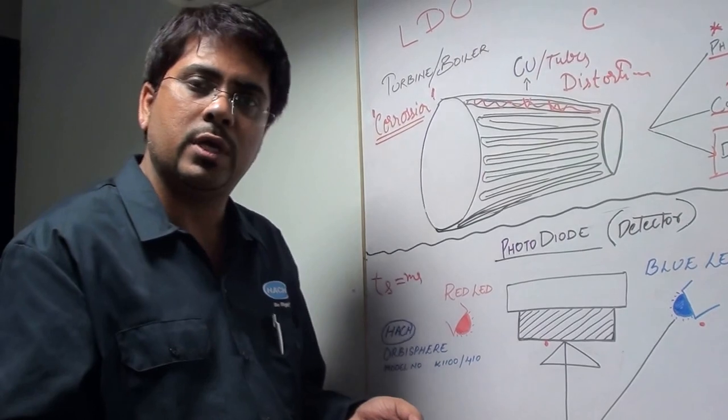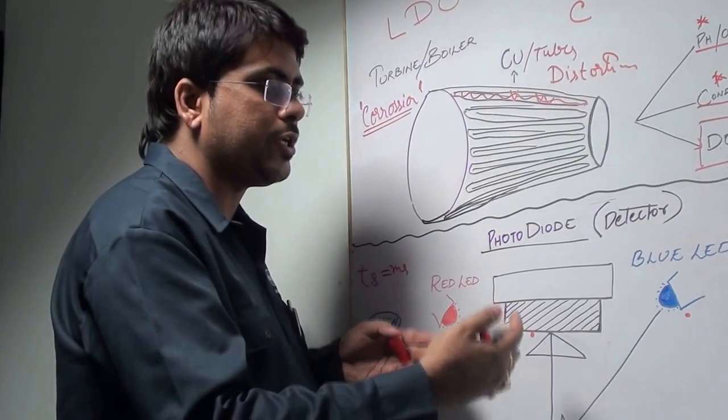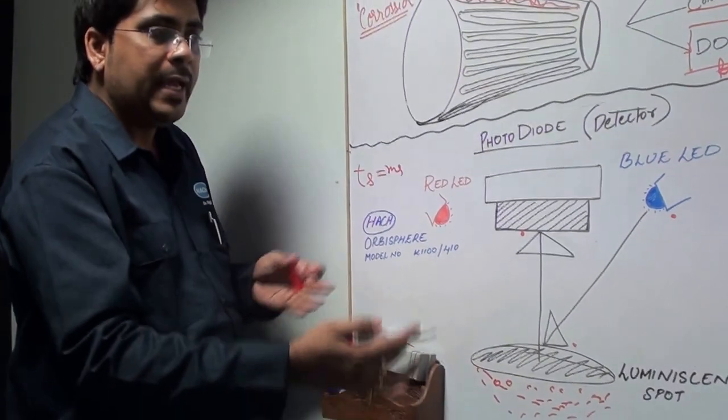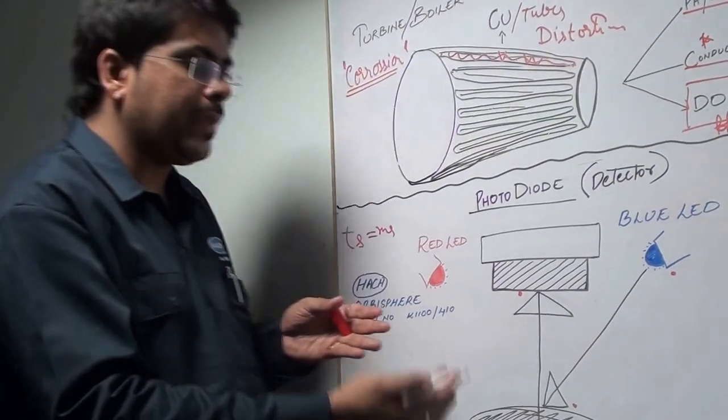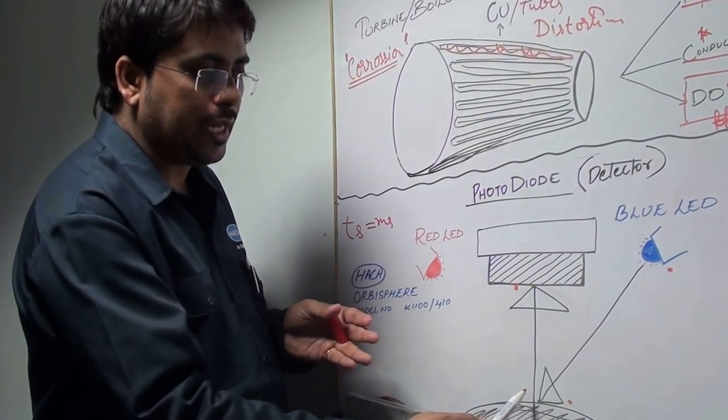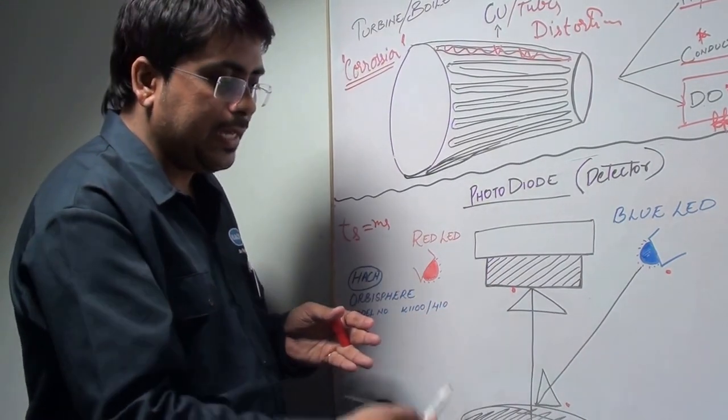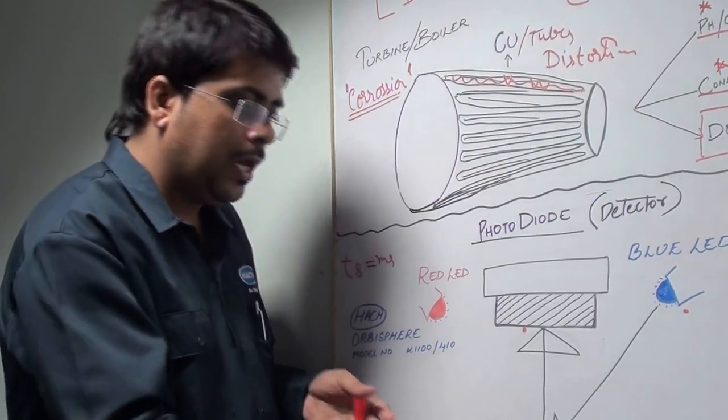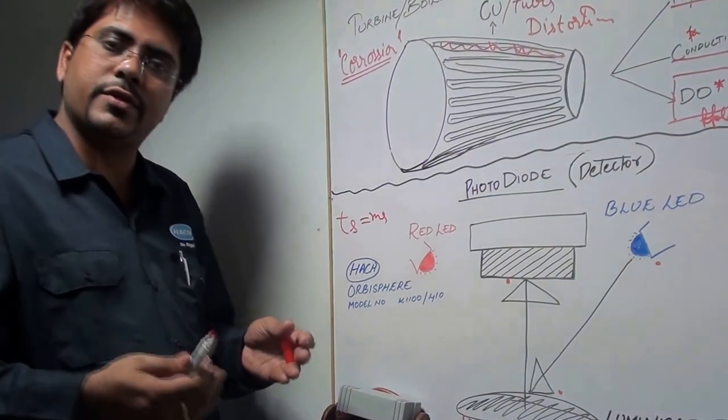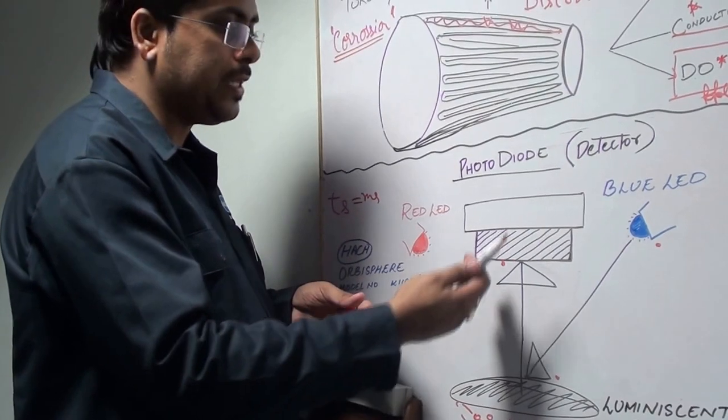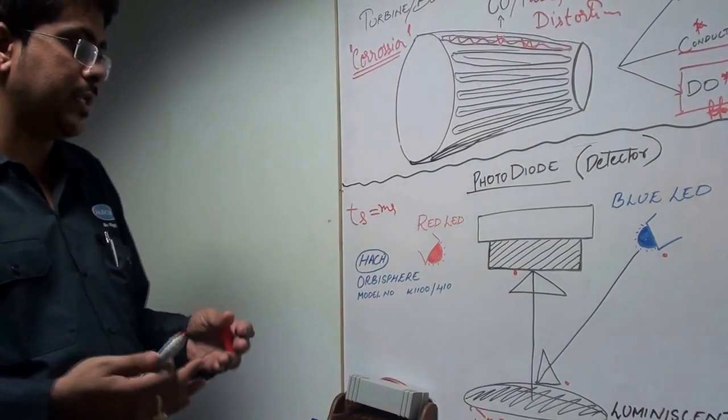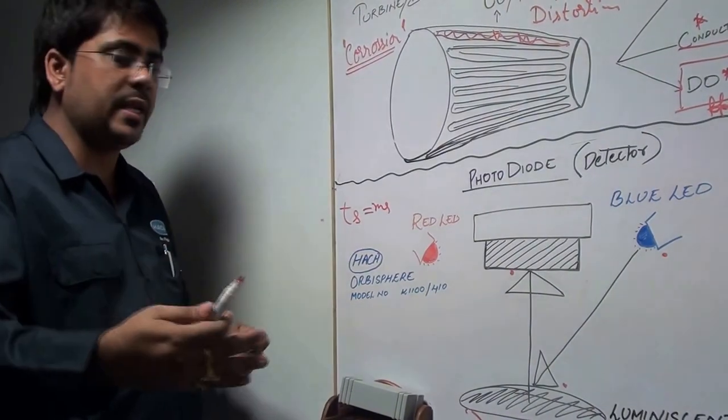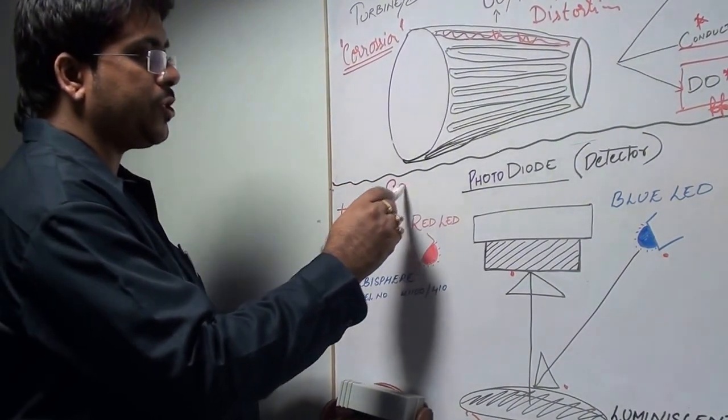This phase shift difference is being converted into the standard industrial 4 to 20 milliamp current output, and it gives your accurate concentration measurement of oxygen. When the concentration of oxygen in the sample is more, it will take very little time for the radiation of light to get detected at the detector, and the optical spot will get de-excited pretty fast. Conversely, when the oxygen concentration is less, it takes longer time to get detected. This time difference or phase shift is being converted to the relative 4 to 20 milliamp output to denote the concentration of dissolved oxygen in PPB.